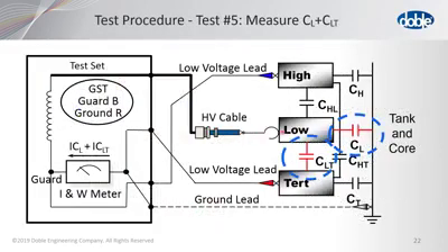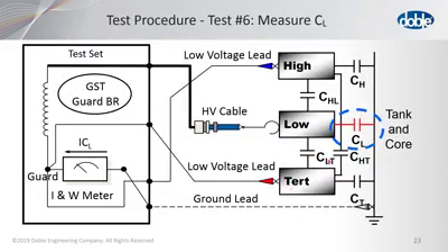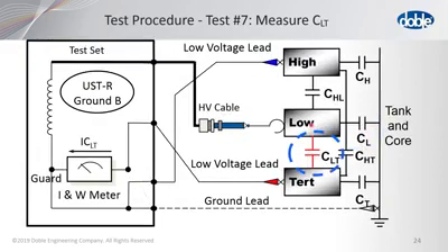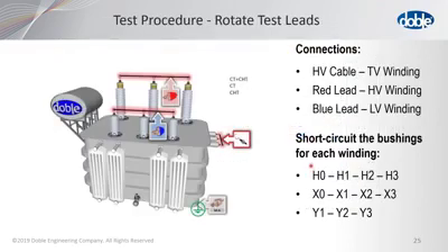And again, it's written up in DTA, the connections. The shorting of the bushings remains the same. Now we're energizing the low voltage winding, so we're measuring this two-winding transformer, right? And then, of course, we go to test number 6, where we measure only the low voltage winding to ground. Then we change it to the 7th test, and notice that we now go from the low to tertiary. Okay, so we've got the second two-winding transformer completed.